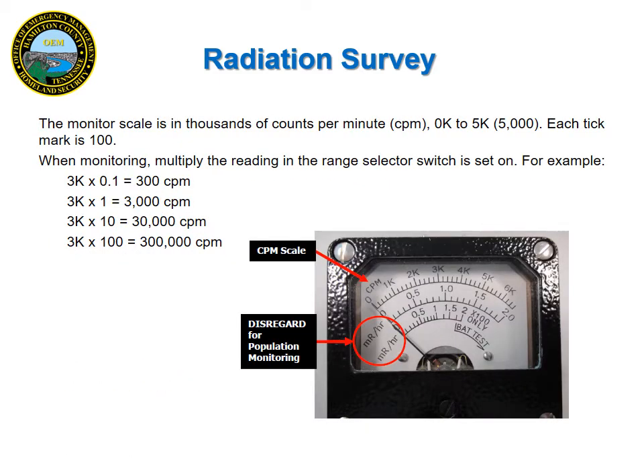Okay, so knowing how to read the Ludlum monitor scale correctly is probably the most difficult part of using this monitor. The first thing to know is that the Ludlum measures in counts per minute, or CPM for short. The scale on the meter is between 0K and 5K, as you can see. So 5 is going to be 5,000. Each tick mark is 100.